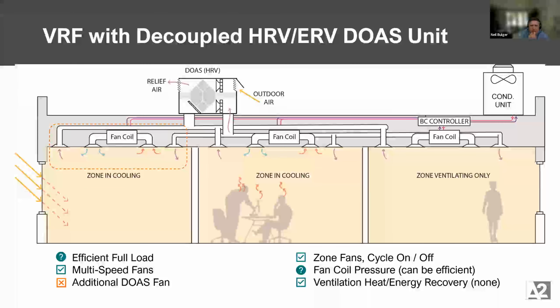And then lastly, the system that is certainly hard to engineer, as much as I like it for efficiency. I do respect the challenge, which is overly expressed in this diagram, of trying to ventilate a room with dedicated decoupled air. So trying to bring the fresh air in and having enough space to put all those different registers in the ceiling of each room. You need fresh air in, fresh air out, cooling in, cooling out. But you get a lot of performance, right?